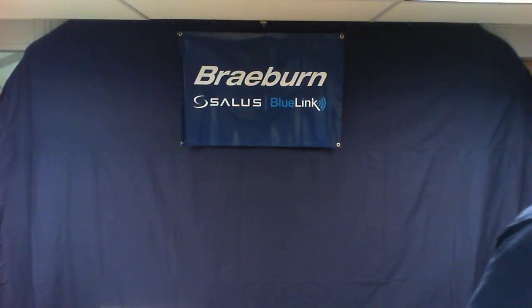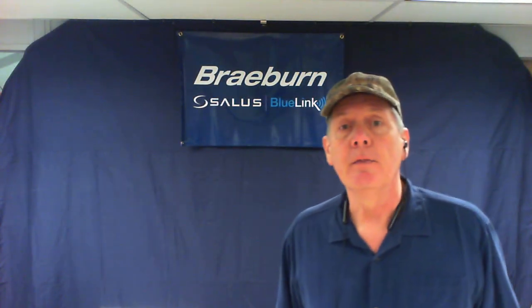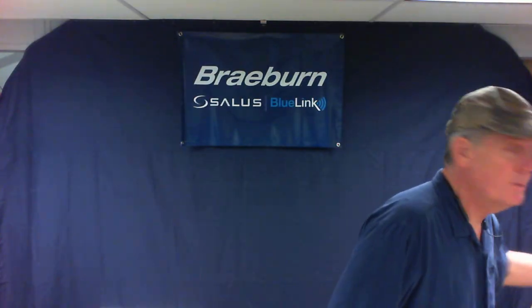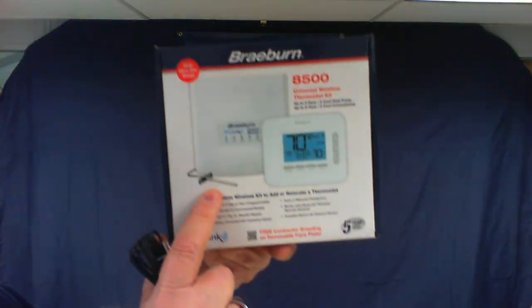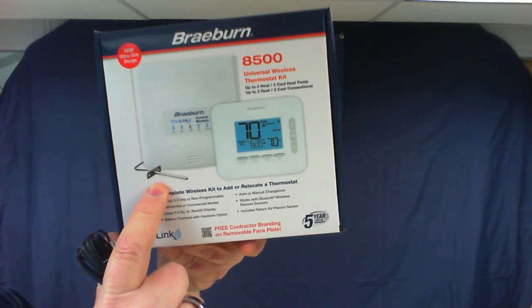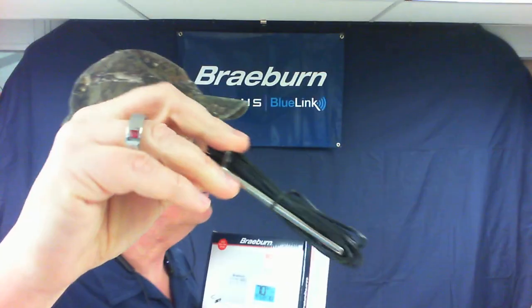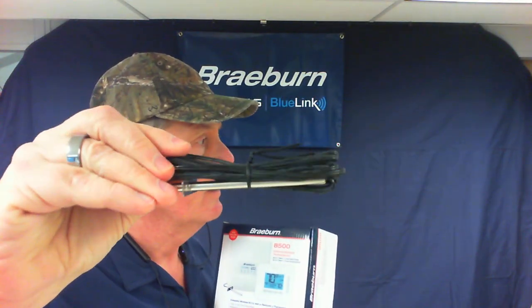So what are we talking about? We are talking about the plenum sensor. I get a lot of calls about the plenum sensor, a lot of confusion, a lot of misunderstanding about what it is, what it's for, how it works. The plenum sensor is included in the kit. It's this little metal probe that you see right here on the cover of the box. Comes in the box. Here it is. It's got about 6 feet of wire on it.